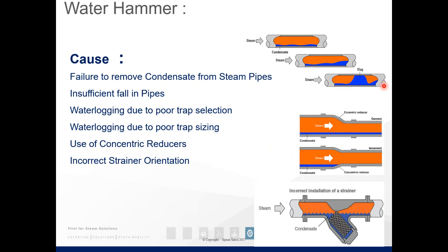Now this can move at up to Mach 1. So if you imagine Tom Cruise in his fighter jet flying down your condensate pipe and then hitting a closed isolation valve, or a trap, or a control valve. Not only would it make a mess of Tom Cruise, it makes a mess of your steam system. So yes, it could be moving at Mach 1. Failure to remove condensate can be the cause of this.